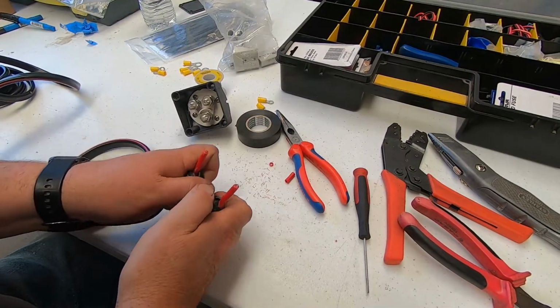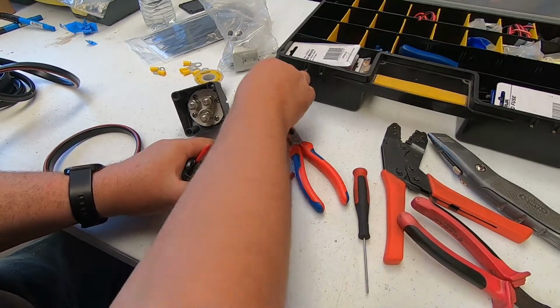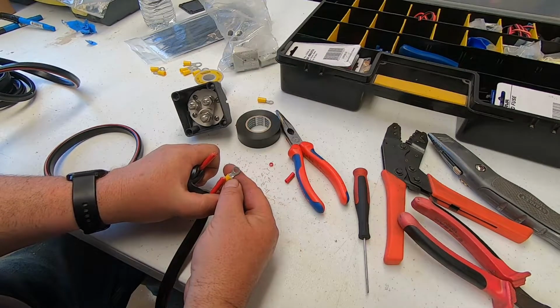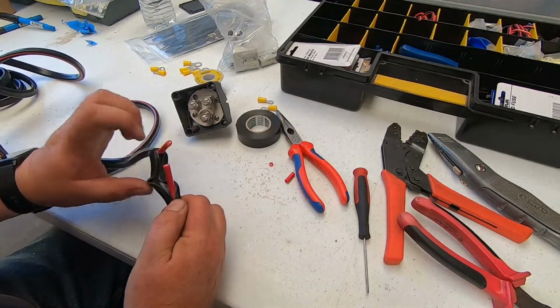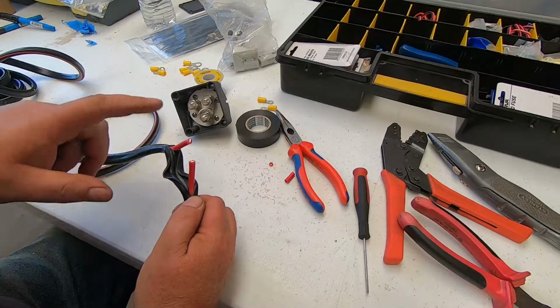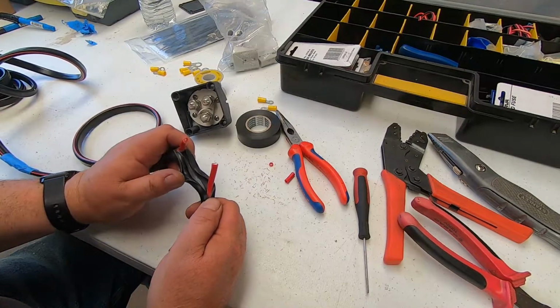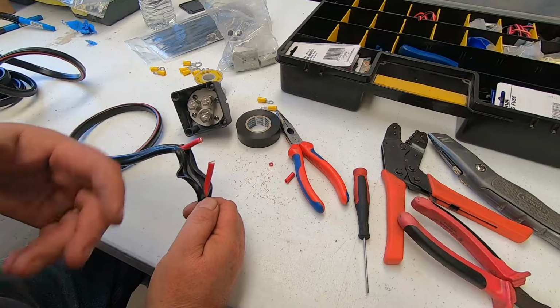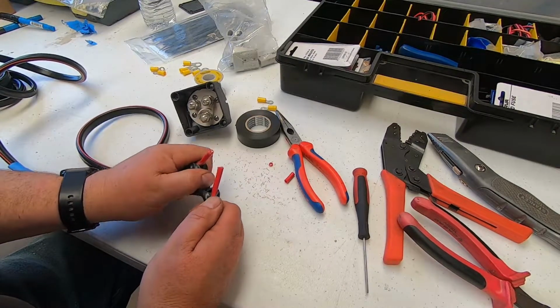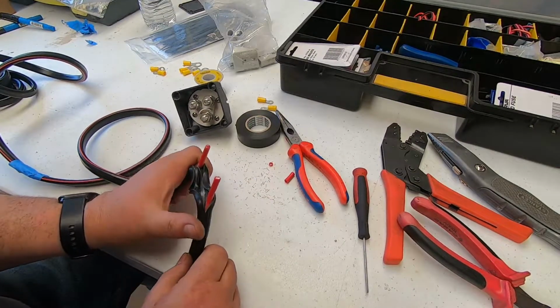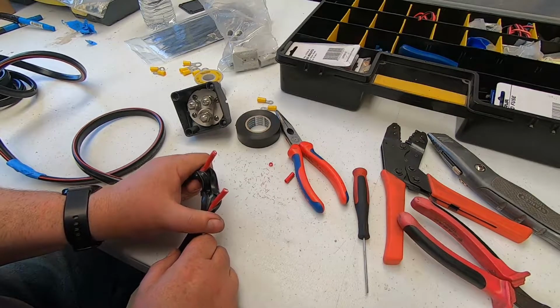So this is just going to bridge this little circuit breaker we just mounted, and these terminals will just go on here. So what that means is you've got a constant flow with your earth wire as well, with minimum breaks in any of the cables, because every time you cut an earth wire you're going to rejoin it. It's just an extra connection that can lead to corrosion and poor connectivity and cause problems.